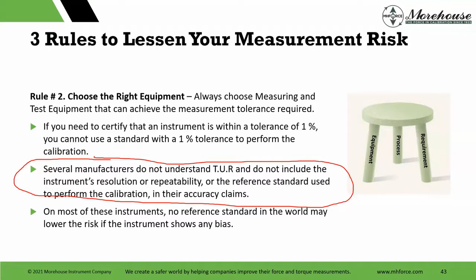Like, hey, I can do that. I'll put this thing over here. Someone says this should be good enough to calibrate this. Yep, it's good, and they give it to you. On most of these instruments, no reference standard in the world may lower risk if the instrument shows any bias. I'm going to show you an example. This happens. This is a scale. The scale is repeatable within 10 pounds and has a resolution of 10 pounds. No matter what reference standard is used, the total risk will always be higher than 10% unless actions are taken.